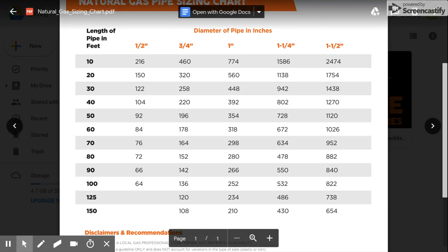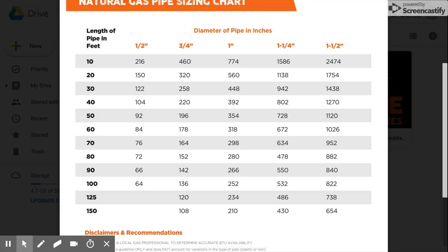So assume you are about 60 feet away and you have a three-quarter inch line. You are approximately 178,000 BTUs.